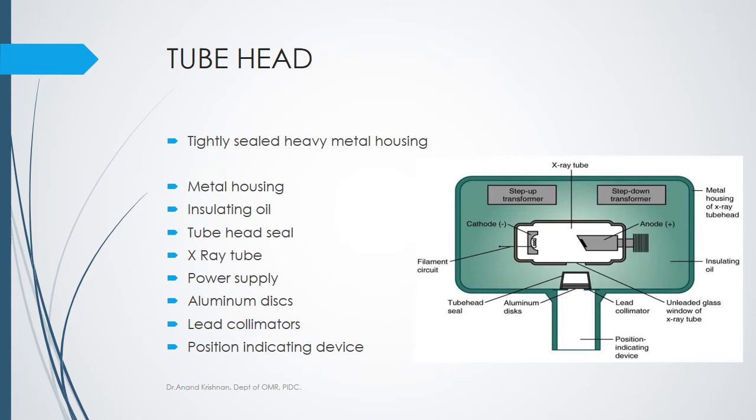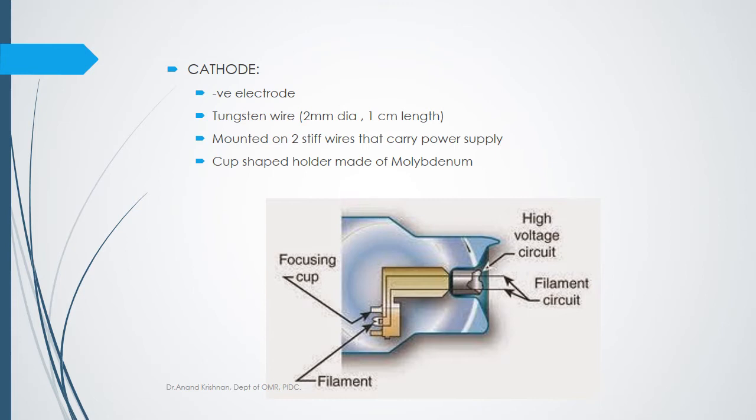Within the tube we have the negative cathode, the positive anode, and a lead glass housing within which the tube is kept in vacuum, because the presence of any air particles will influence the production of x-rays.